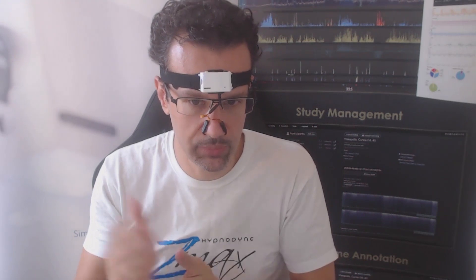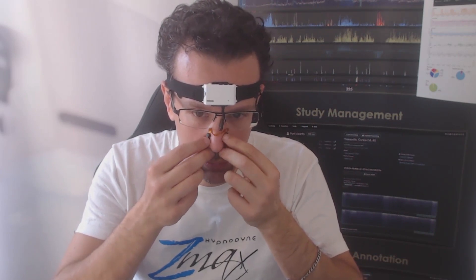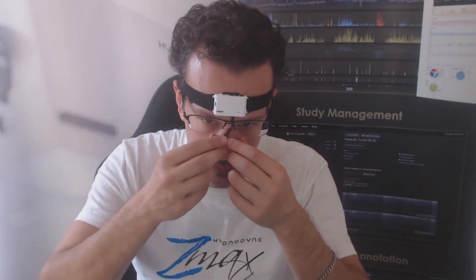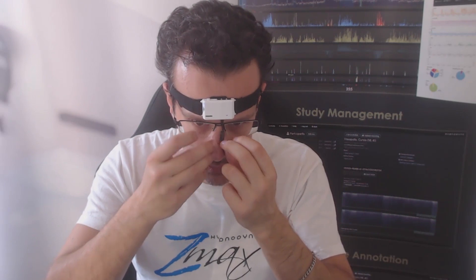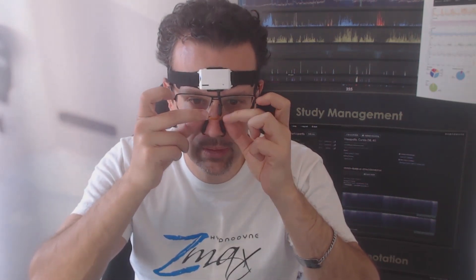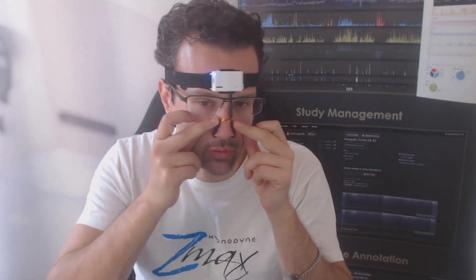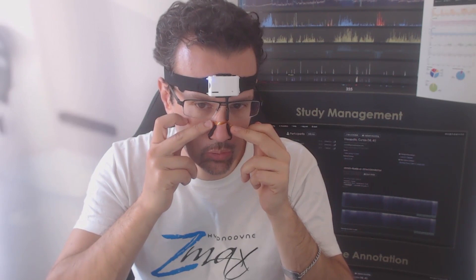So that while the person is breathing, perhaps with their face against the pillow, and as the person is moving around, this doesn't get dislocated. Another thing that could easily happen is that if you leave this hanging in front of you, it will rhythmically — with your breathing rhythm — hit against the pillow and produce some waveform that's not really good. So now it's on my face, and it's not in a condition where I can actually show you how to shorten it, but you can imagine this flat cable being bent in half, and then you apply some tape to shorten it.